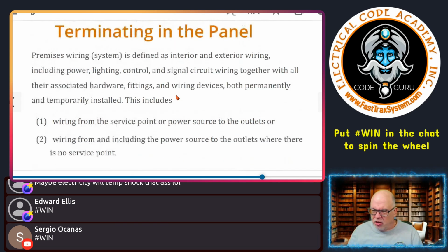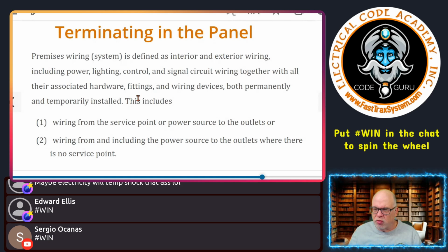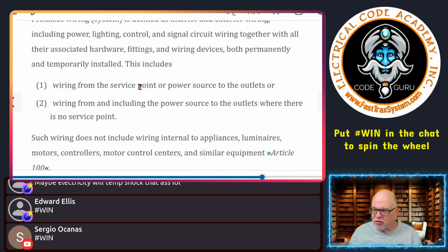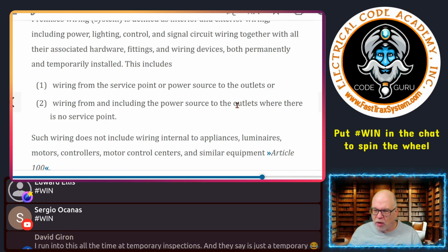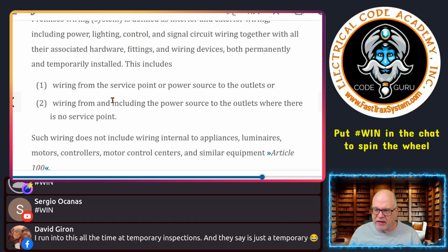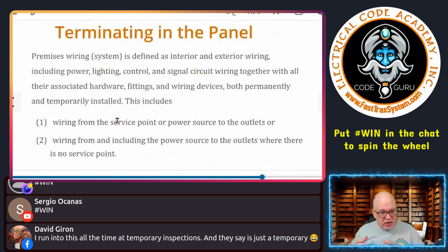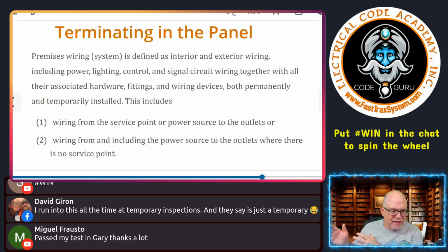All right, so what does this include? It includes wiring from the service point or power source to the outlets, or wiring from and including the power source to outlets where there is no service point, okay? So, again, all this is saying is that at the end of the day, temporary has no special rules when it comes to this. You have temporary allowances for using certain types of wiring methods up in 590, right? Okay, but that's it.